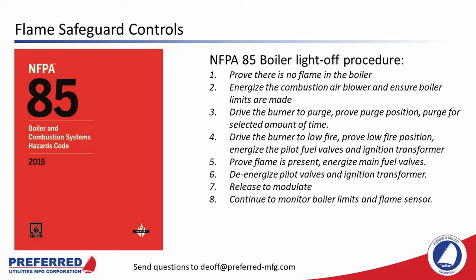NFPA 85 provides very specific rules governing the shutdown, light-off, and monitoring of boilers 12.5 million BTUs per hour and larger. Smaller boilers are covered by CSD1 — controls and safety devices for automatically fired boilers. The two codes are very similar, but if you're going to be working on boilers in these size ranges, you need to know the specifics of both codes.